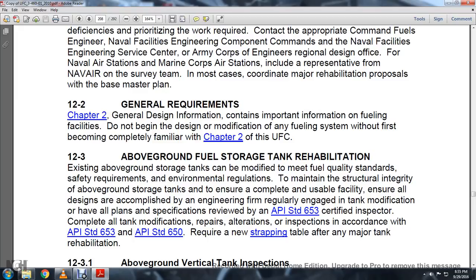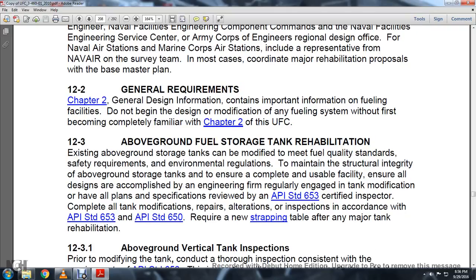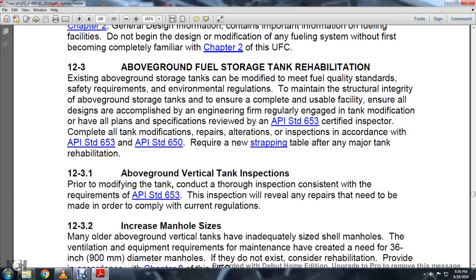Section 12-3: Above-Ground Fuel Storage Rehabilitation. Existing above-ground tanks can be modified to meet fuel quality standards, safety requirements, and environmental regulations, and to maintain structural integrity. Ensure all design and engineering modifications to tanks are reviewed and that an API Standard 653 certified inspector completes all tank modifications and prepares alterations inspection in accordance with API Standard 653 and API Standard 650. Require a new strapping table after major tank rehabilitation. Prior to modification, conduct a thorough inspection consistent with API Standard 653.